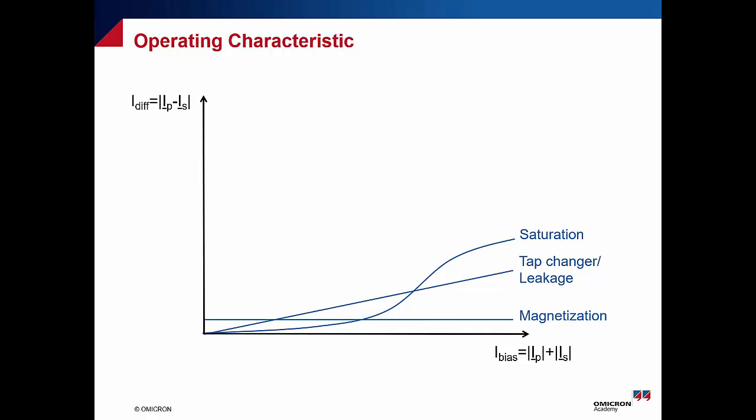As we see here, with a heavy external fault it can cause a kind of partial saturation, which can push the differential protection relay to misoperate. But for sure, we know that new digital and numerical protection relays have internal compensation for this kind of saturation.